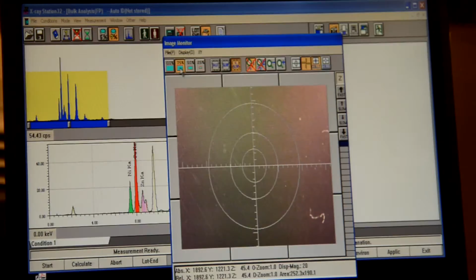I was making a measurement with the vacuum, and there was a composition. Right now it is showing me the percentage of the specimen, so that would be 9.49% of nickel. We have zinc, gold, and copper. The conditions are time 50 seconds, which is plenty, voltage 45,000 volts, current 8 microamps. It's collimated. That means we're dealing with X-rays coming from the specimen that are not aligned; they're not going to go to the detector. And the environment is vacuum. I'm going to go here one more time so we can see much better and show how that works.